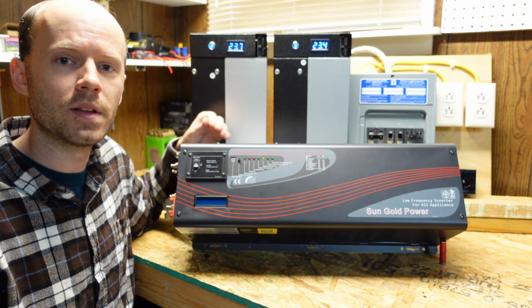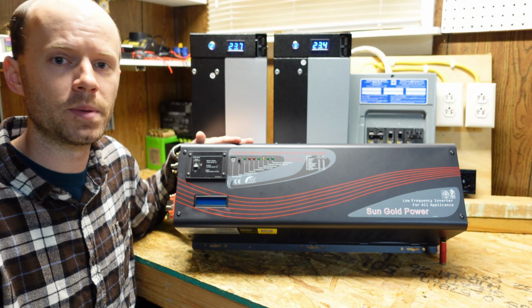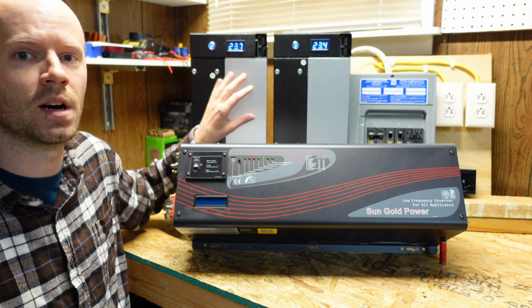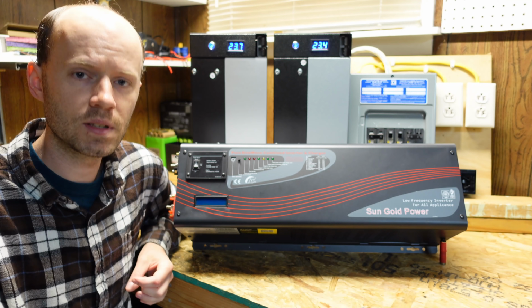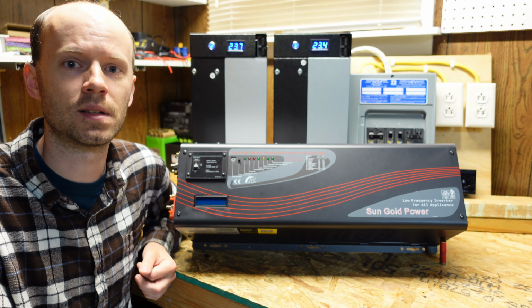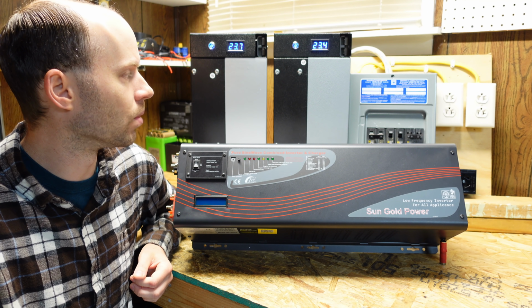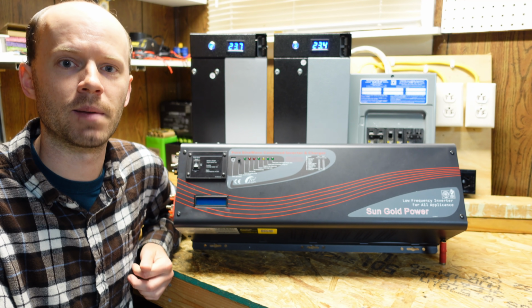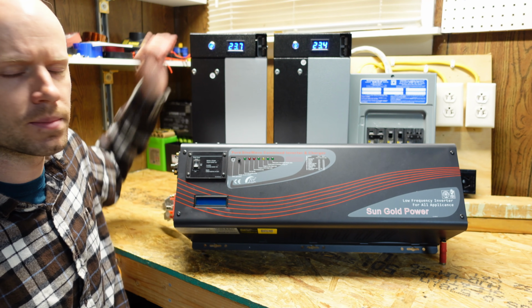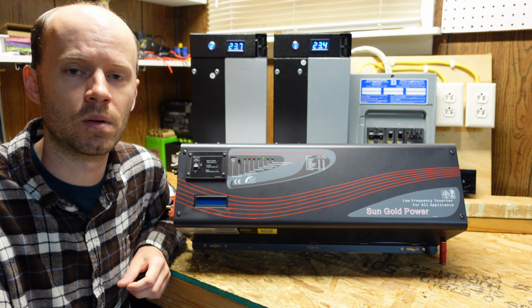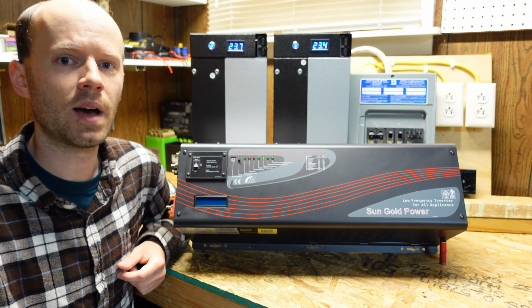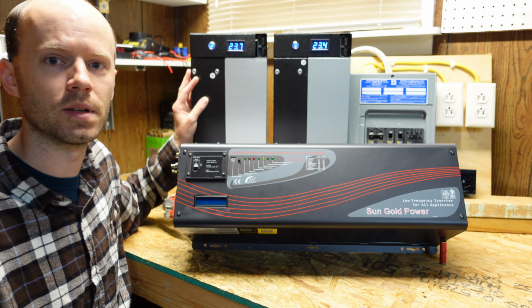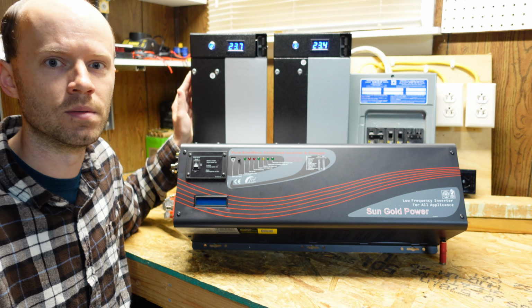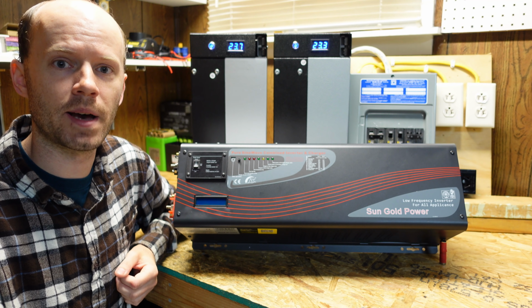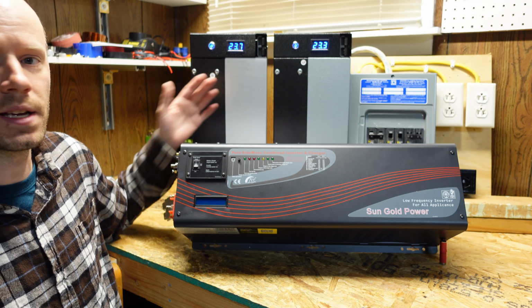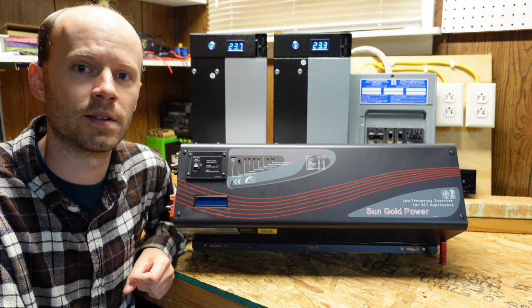Now this video is about this inverter, however I was a little bit disappointed to see these batteries could not push the 130 amps continuous they are rated for. 6 gauge wire, even if it is silicone insulated, just is not enough for 130 amps in my opinion. So I don't know if it was maybe the crimps or something in there that were getting a little bit warm, so the whole wire was getting warm, but either way, I would have definitely preferred to see this battery built with number 4 or maybe even number 2. Nevertheless, it's still a fantastic battery. I have no problem with 75, 80 amps, something like that through it, but not 110 or not 130.